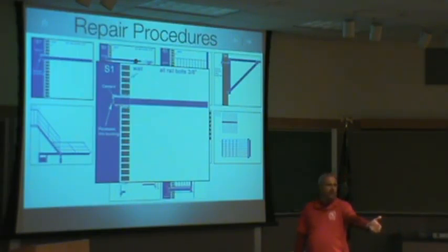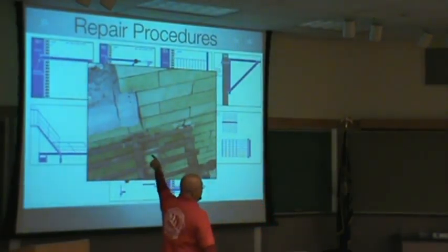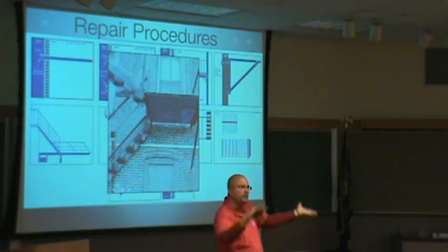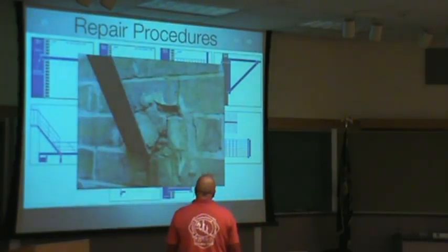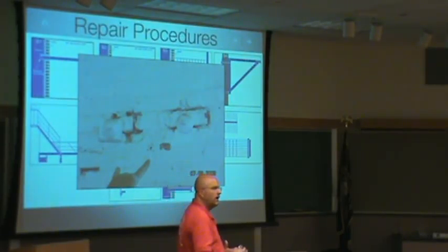That's what this class is all about — finding where you have the power. Who has the power to oversee what gets done to a fire escape? The owner, the structural engineer, or you? That's you guys — we have the power. That's how deep it is into the building: 8 to 12 inches deep — a cemented pocket, that's what it looks like. Two staircases with dangling treads — and where's the brace? Somebody took it up and put it back. As soon as you step on that, if it's only 8 to 12 inches deep into the wall, how much weight are you going to need to rip it out? This is the typical — it either has a single bolt or a gusset, still only buried 8 to 12 inches deep. This needs to be refurbished, and that needs to be either verified or duplicated.